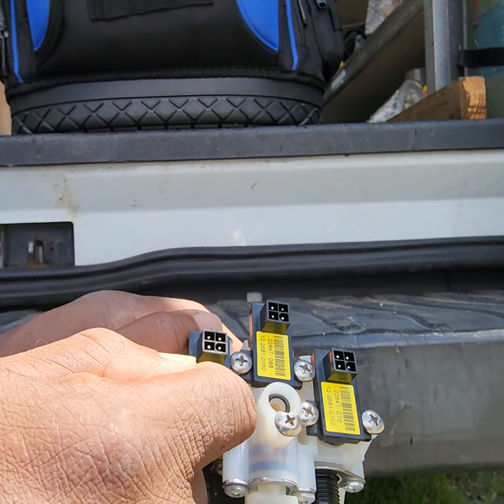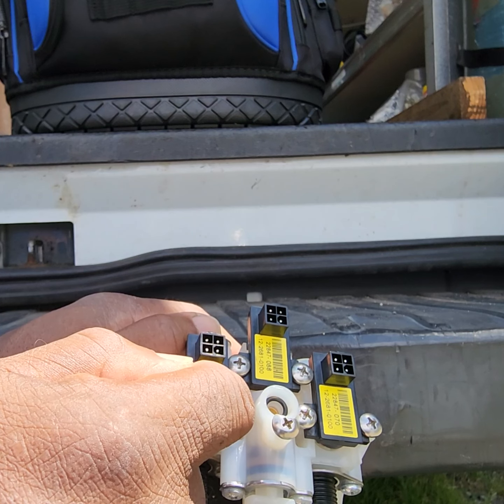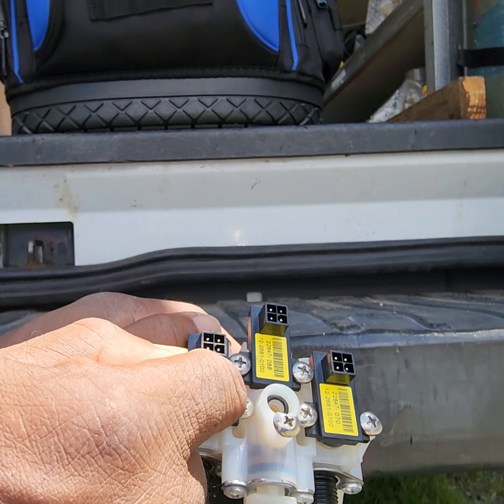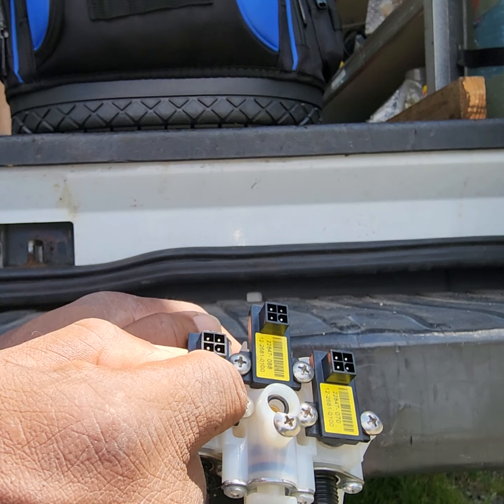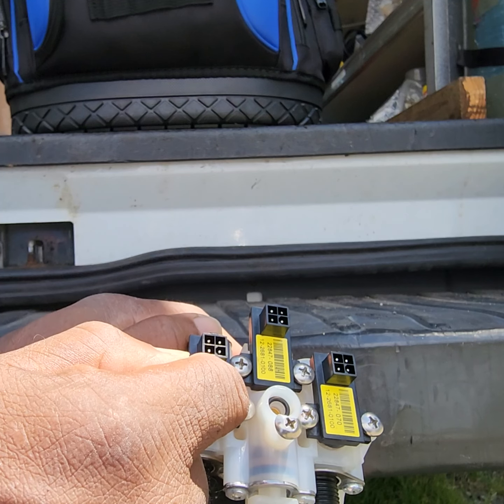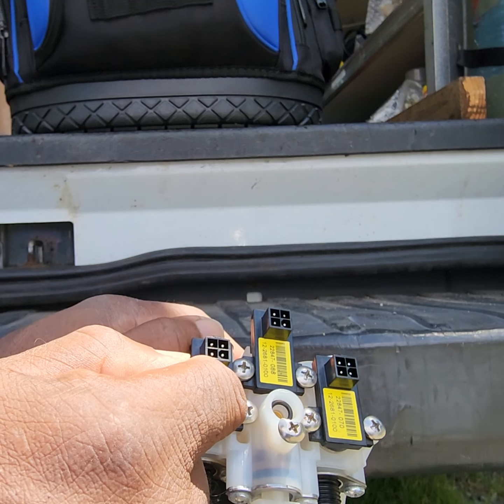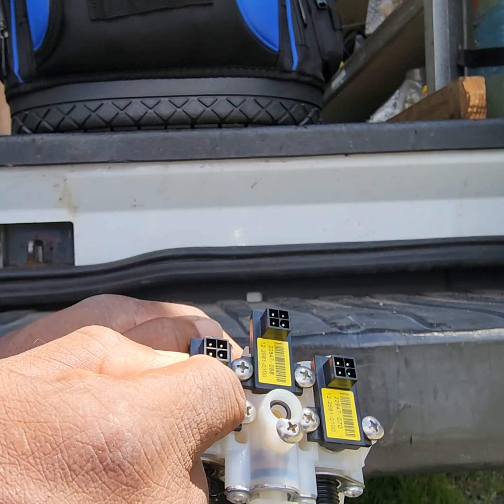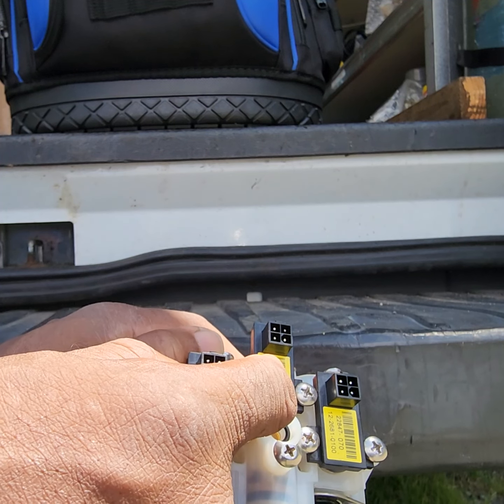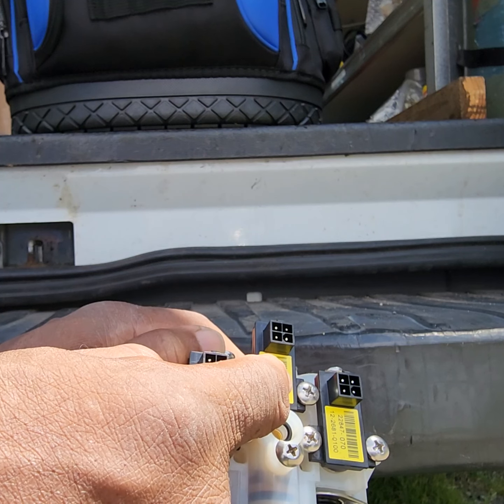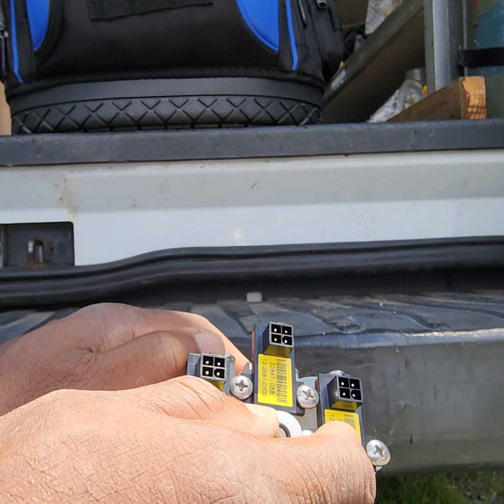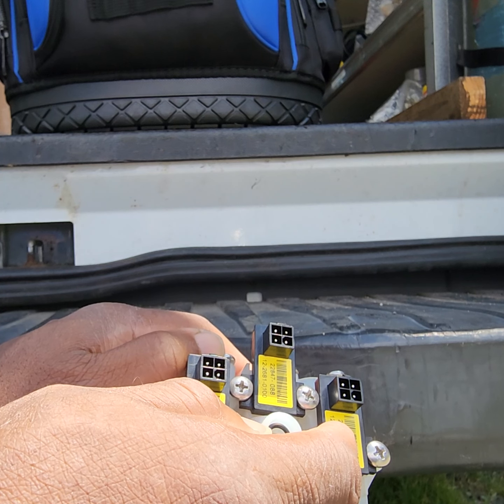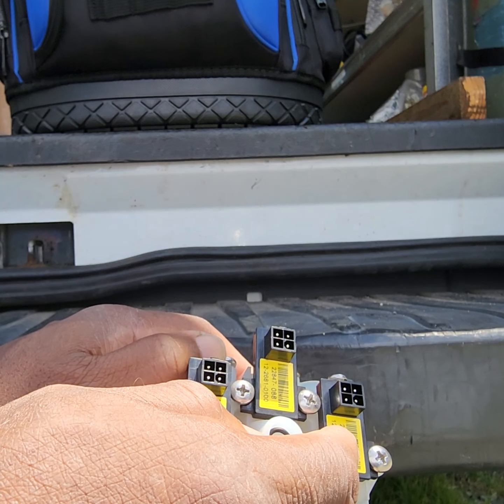Your water should be over 60 psi. Okay, preferably it should be around between 80 or 90. Your tank pressure should be around 30, and then your syrup pressure, that should be around 70 psi.